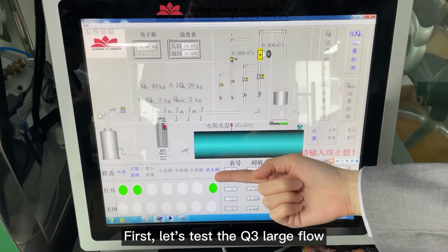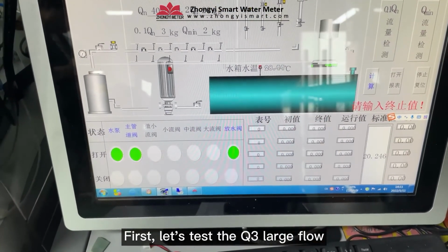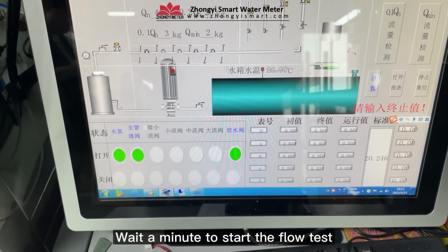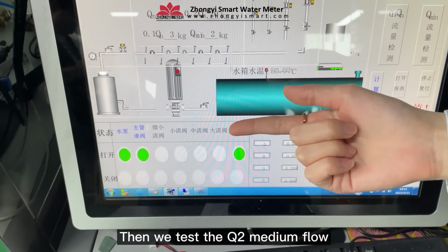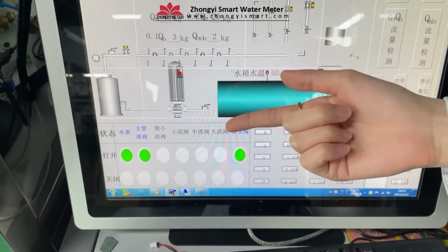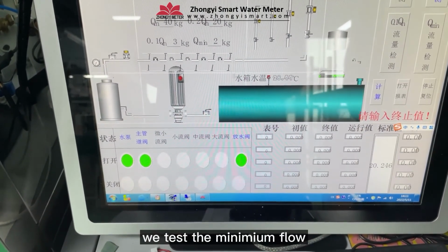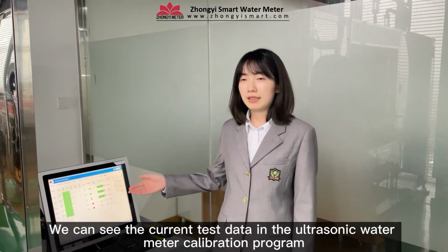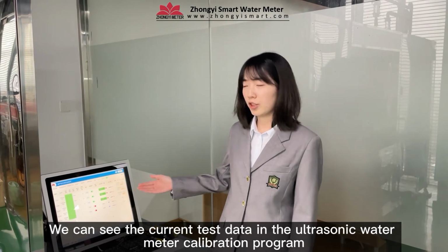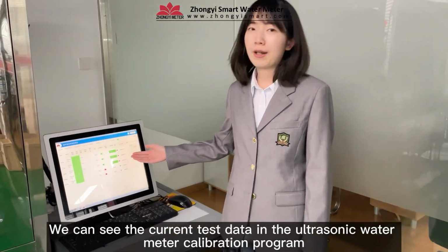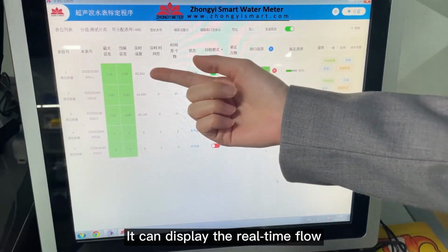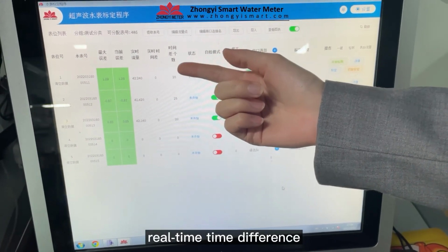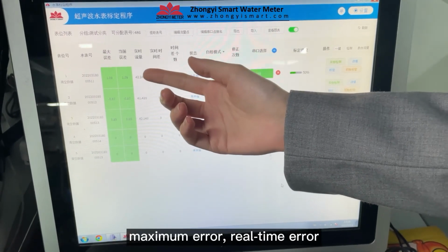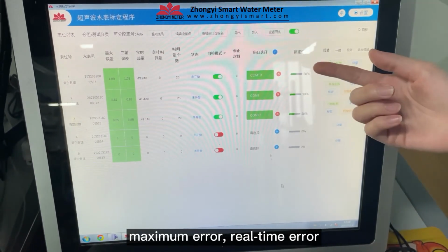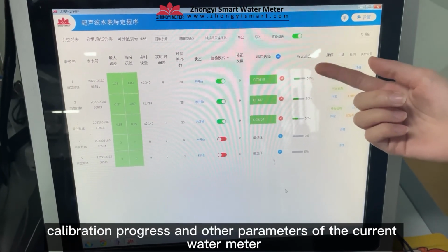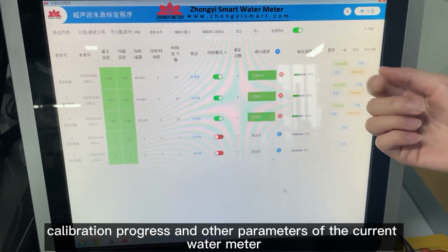First, let's test the Q3 large flow. Wait a minute to start the flow test. Then we test the Q2 medium flow. At last, we test the minimum flow. We can see the current test data in the ultrasonic water meter calibration program. It can display the real-time flow, real-time time difference, maximum error, real-time error, calibration progress, and other parameters of the current water meter.